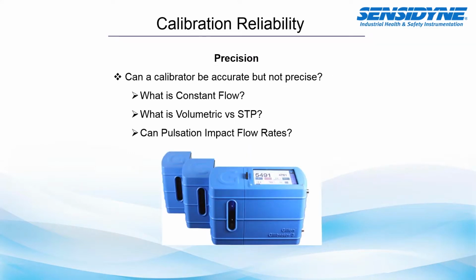So we talk about, can a calibrator be accurate but not precise? Well, many different things can influence why it might be accurate but not precise, or precise but not accurate. One of the things we should consider is constant flow. We may also want to consider if we're looking at volumetric versus STP, which is a standard temperature and pressure, which may be referenced, or if pulsation can impact the flow rate itself. And we'll talk a little bit more about these three aspects that could relate to the precision of your calibration for field instrumentation.